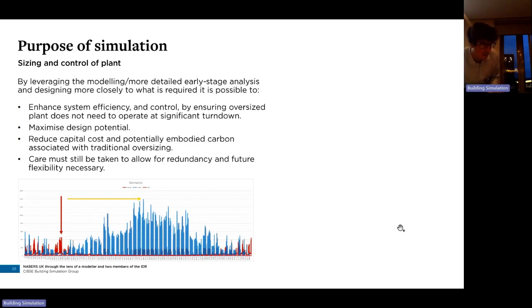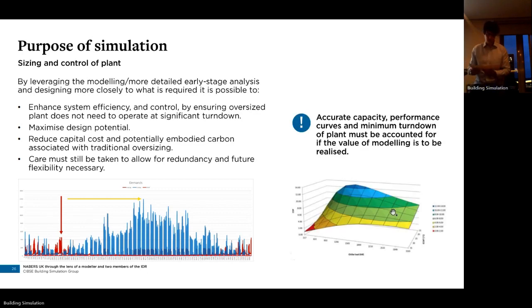As a side note, it's critical that the actual capacity specified, minimum turndown, and accurate performance curves are accurately modelled in the design for performance work. Without this, the modelling will not only fail to reflect the likely outcome and the detriment to efficiency from running plant units at low load, it will also significantly limit the value of the modelling when looking at the implications of alternative options.